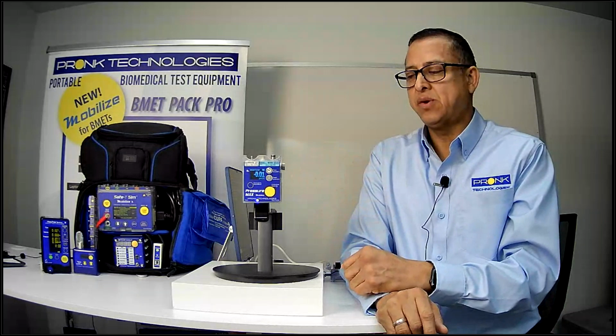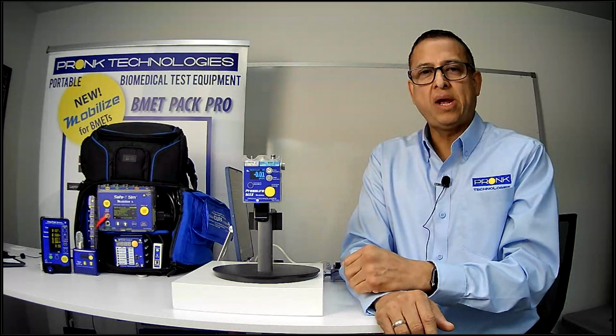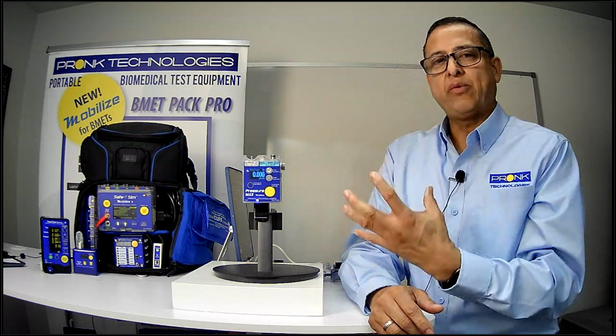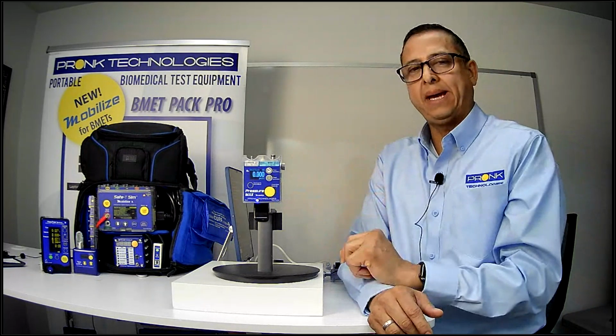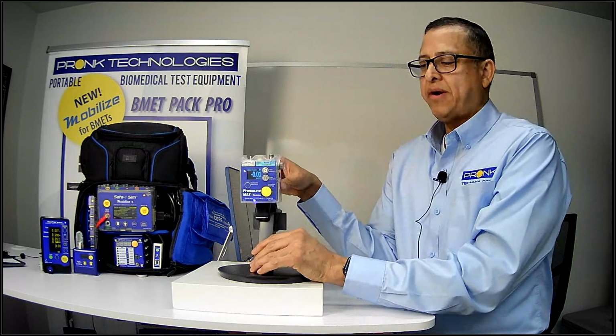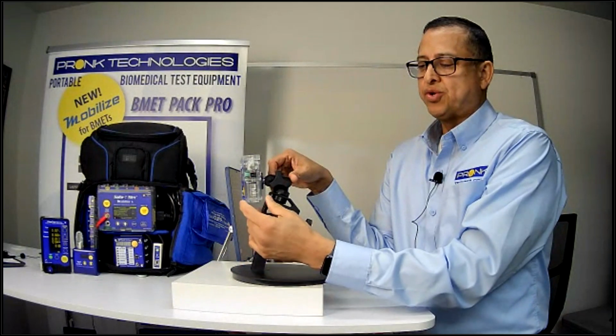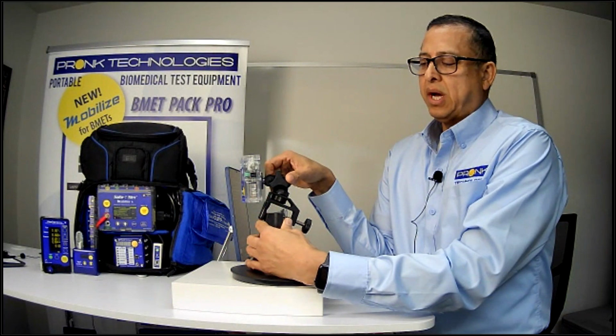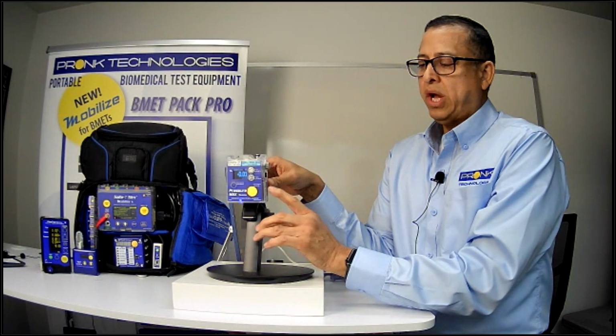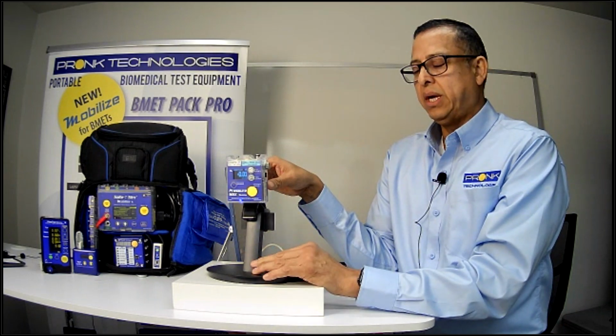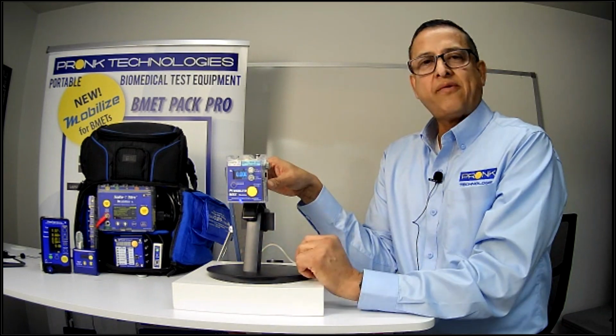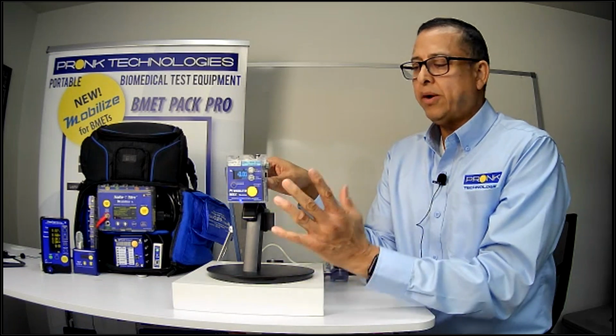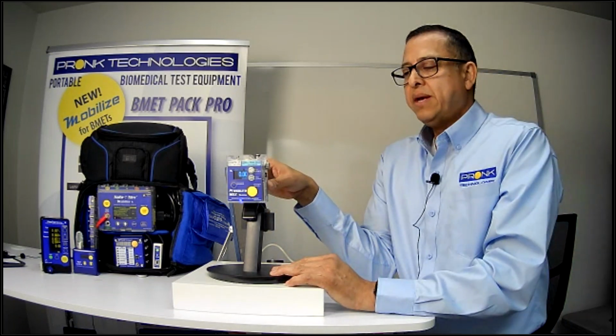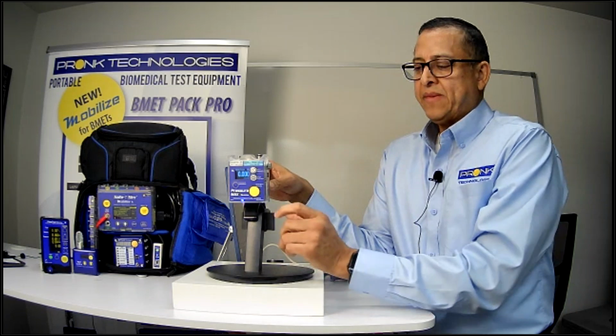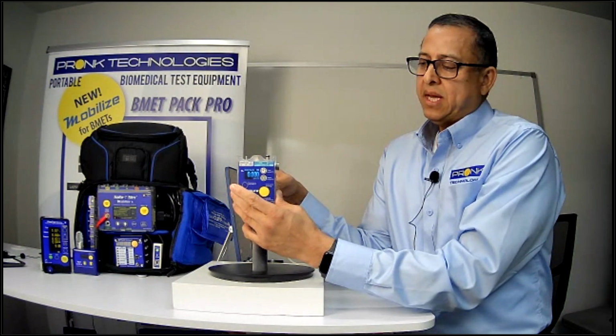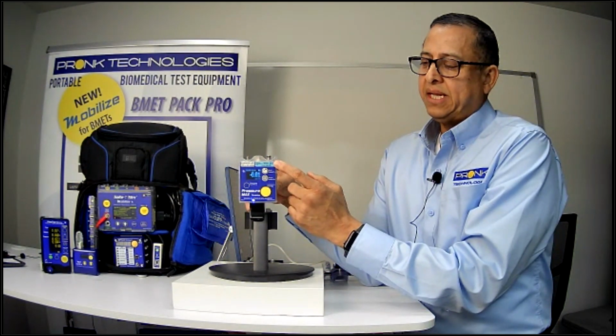Well, Pressure Max is designed to solve this by being a multi-channel pressure meter that gives us the great range and accuracy we need all in one package. You can see here, it's a very small compact device, fits in your shirt pocket, operates on 2 AA batteries, and it runs for about 30 hours continuously in use. The unit does work off of an external 6-volt DC power supply as well, if you want to plug it in and utilize it for long-term testing. So it's very, very compact. You can see there's multiple ports designed into the unit.